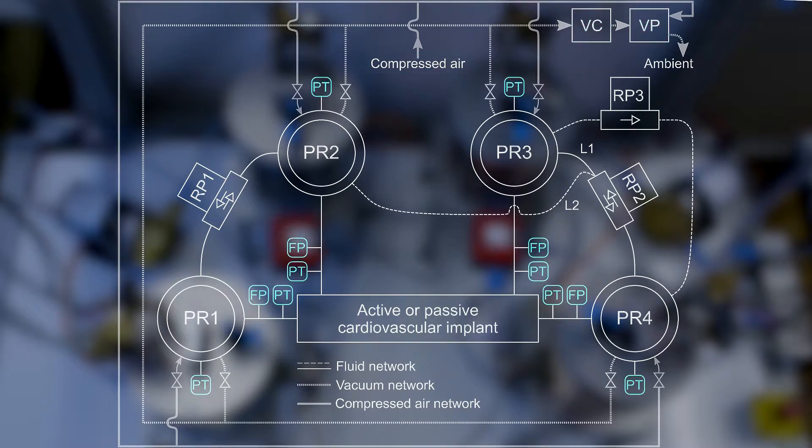The pressures in the reservoirs and the flow through the implant are measured. The flow rate is fed into the numerical model which computes the pressures to be applied to the reservoirs in real time. These pressures interact with the active or passive implant and generate new flow conditions.